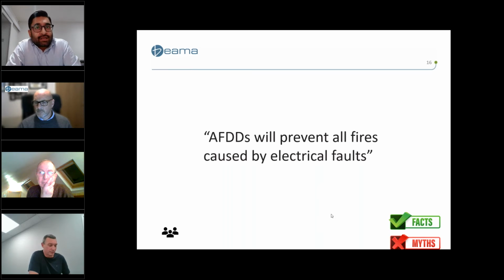I think it's an additional level of protection that we've not had available to us before. We've not used it in many years gone by. This is an additional layer of protection above and beyond what we've become familiar with. Think about the journey where we moved from MCBs to a combination of RCD and MCB. We resulted with the RCBO. This is now an additional layer above and beyond that. We talked about the combination type devices earlier, where you've got a miniature circuit breaker and RCBO coupled with arc fault detection technology. So this is a complementary additional level of protection.